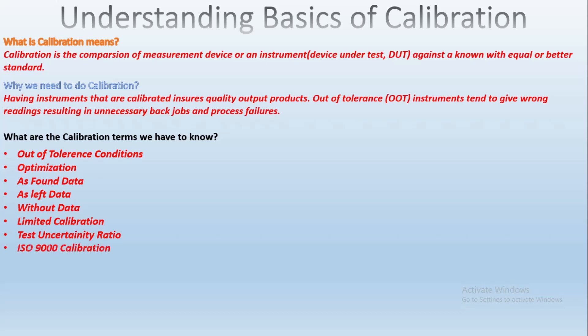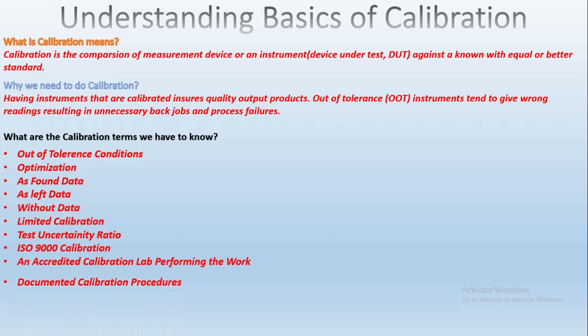The next term is ISO 9000 calibration. ISO 9000 calibrations are crucial for many industries. The following is required for ISO 9000 compliant calibrations. First is an accredited lab: the calibration laboratory employed to perform the calibration must be an ISO 9001:2000 accredited lab, or be the original equipment manufacturer.